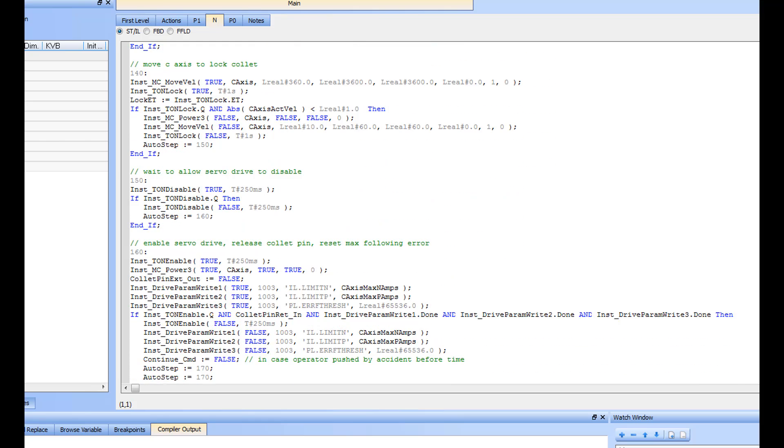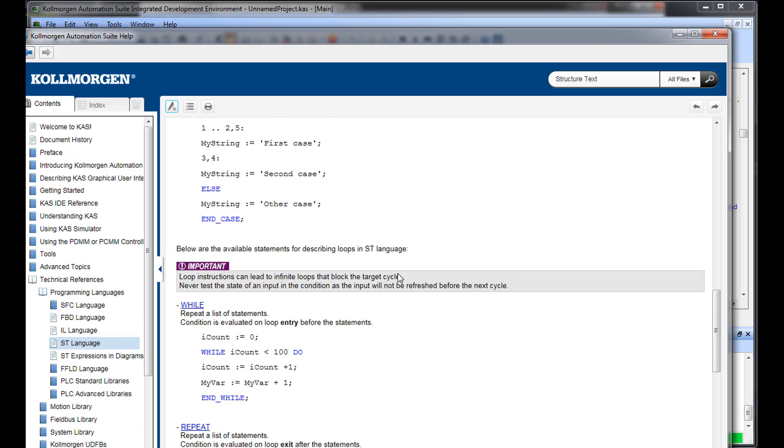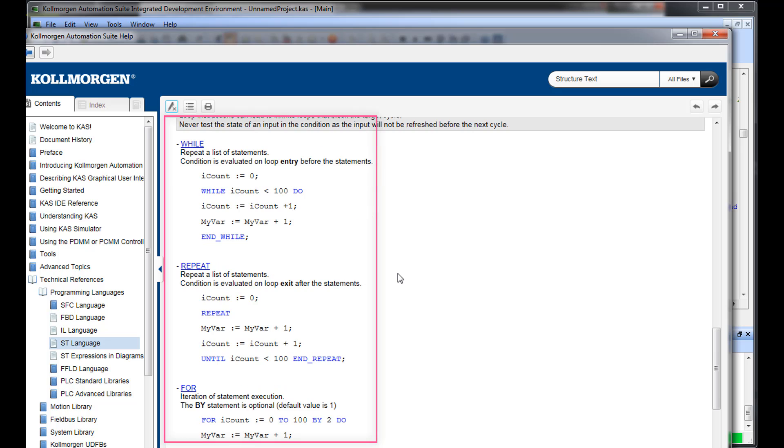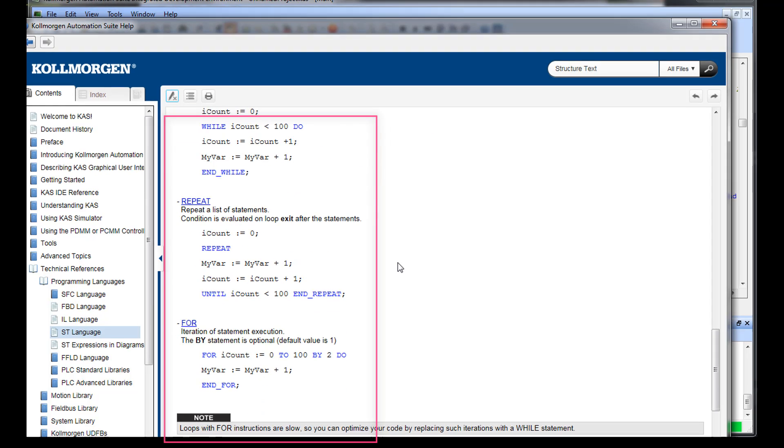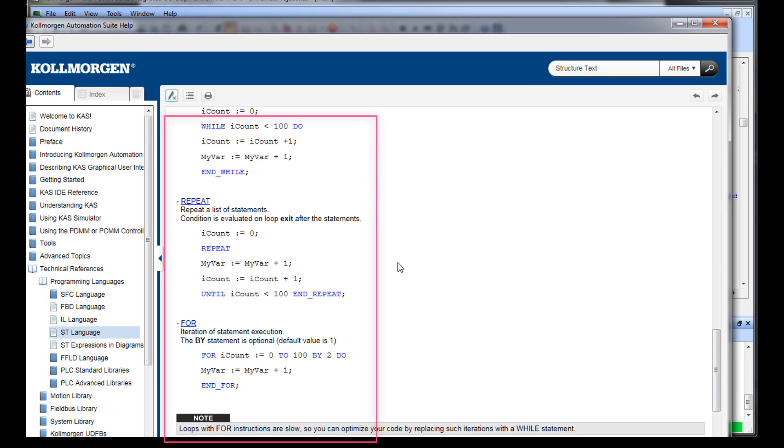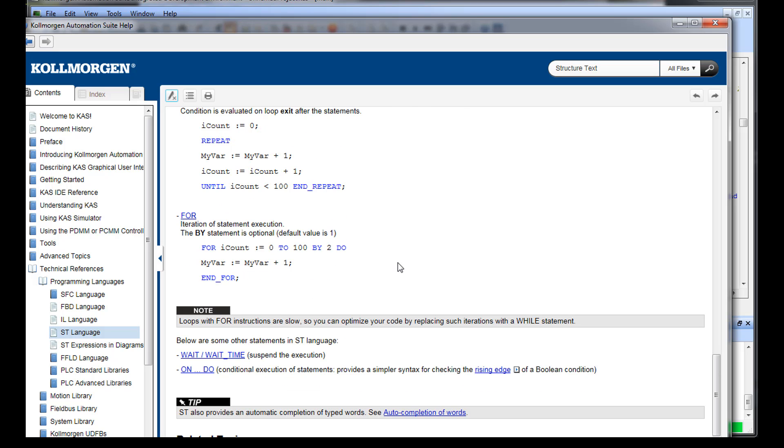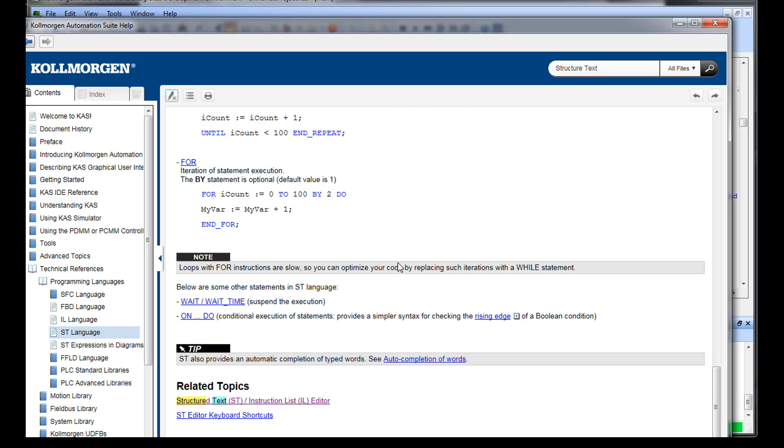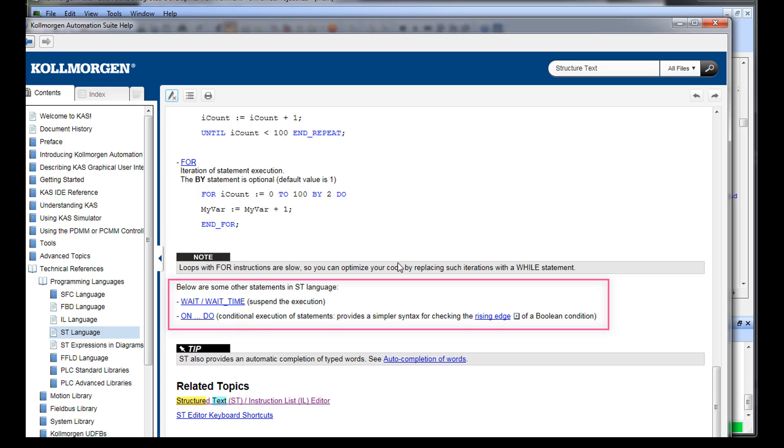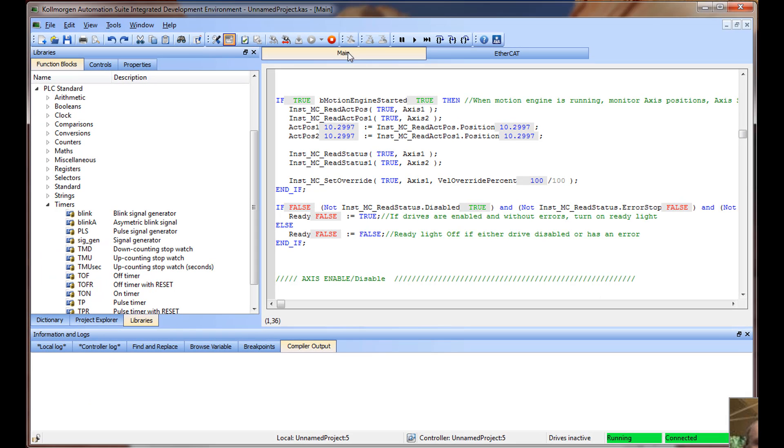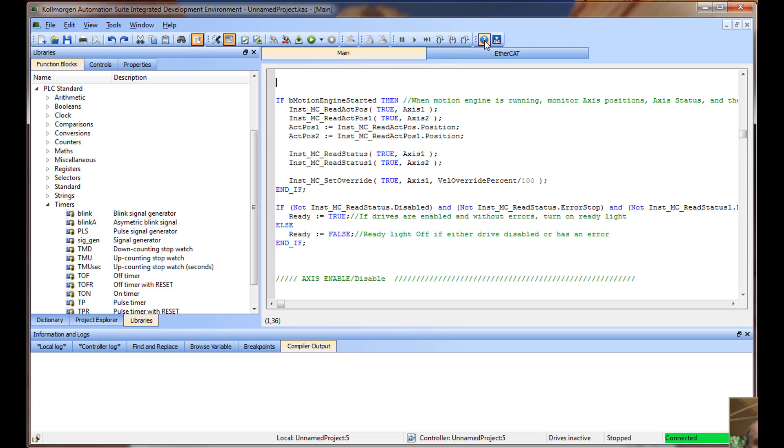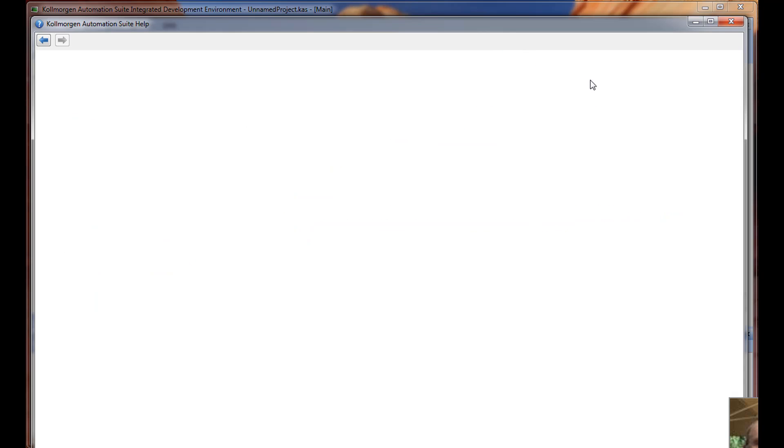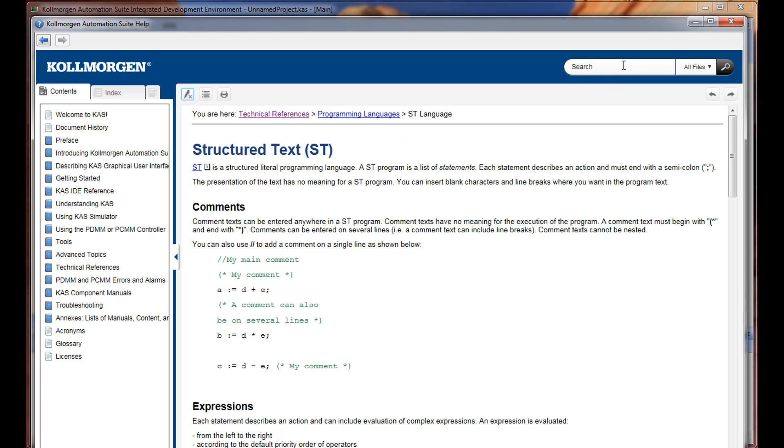For-next, while, repeat-until, and wait can also be used. When using these, care must be taken to make sure conditions will not exist that will add significant time to program execution. On-do and wait statements are not available when structured text code is embedded inside an SFC program. The structured text editor supports shortcut keys for many operations.